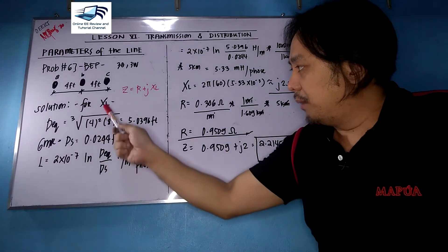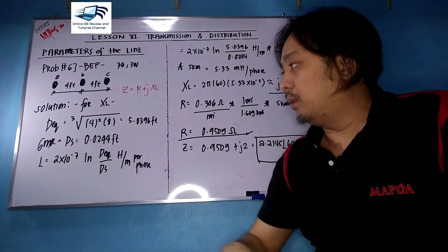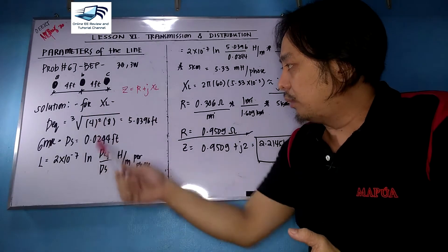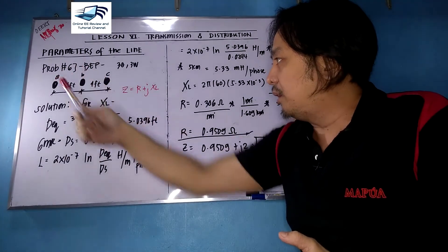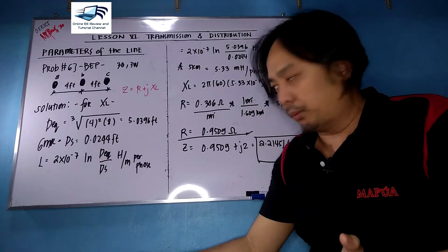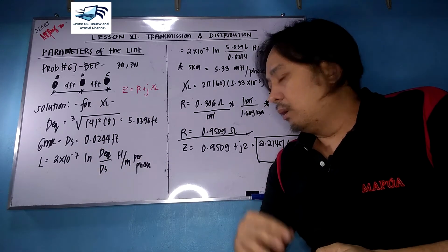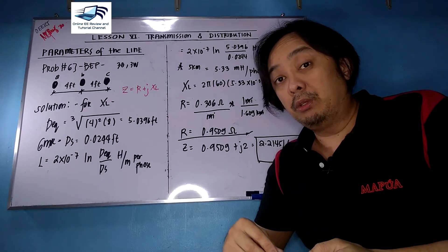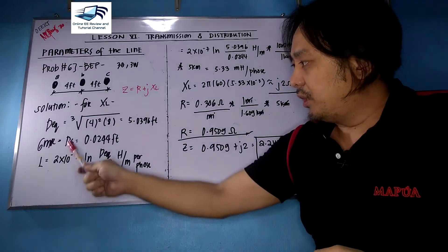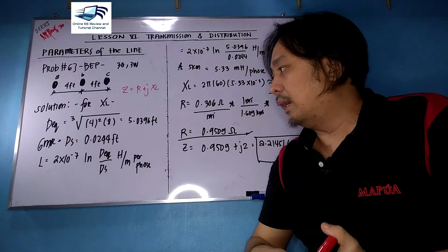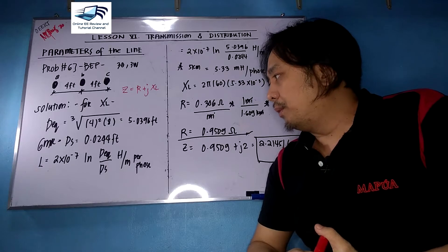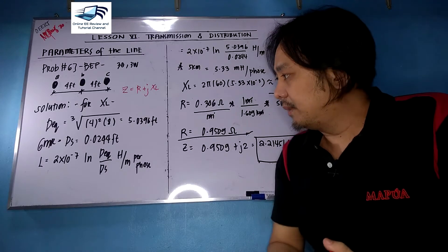To get X_L, we need D_eq. Since conductors A-B and B-C spacings are both four feet, and the A-C return distance is eight feet, D_eq equals the cube root of 4 squared times 8, giving 5.0396 feet. The GMR equals the self-geometric mean distance DS, which is 0.0244 feet.